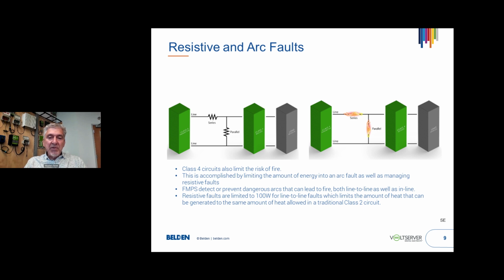Here's another resistive or arc fault depiction. Now, arc faults we're familiar with, to those in the industry that have dealt with AC power. We have arc fault detectors that are also often combined with ground fault or even circuit breaker capabilities. But what has not been detected before in conventional systems up to date is what's called a resistive fault. And many of you probably have, either through your personal experience or through somebody you know, experienced a resistive fault. It occurs often when you might have an AC outlet in your home, and if the screw is not tightened down enough on the wire connecting to the AC outlet, you could develop what's called a glowing connection. It'll start to carbonize and change composition and eventually turn into a heater rather than a conductor.